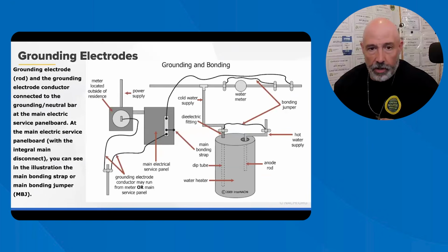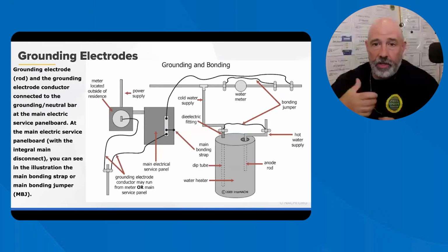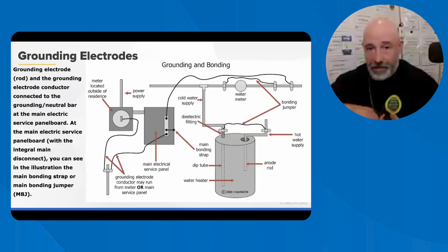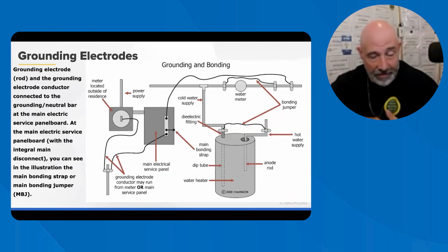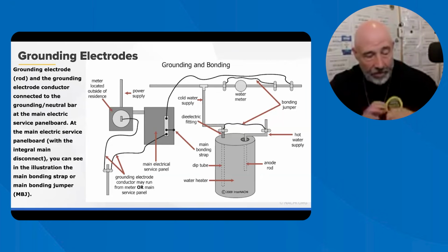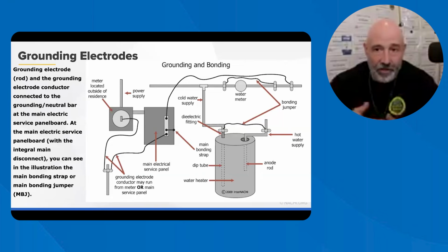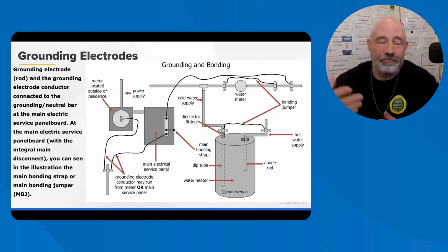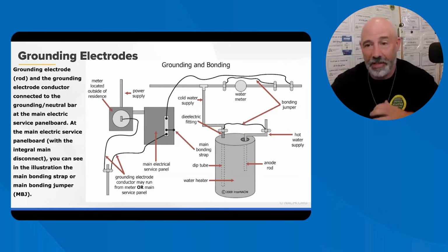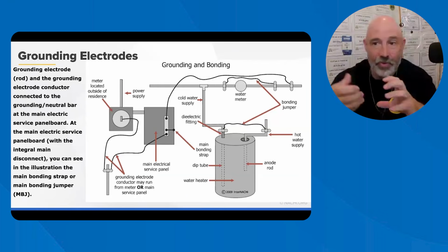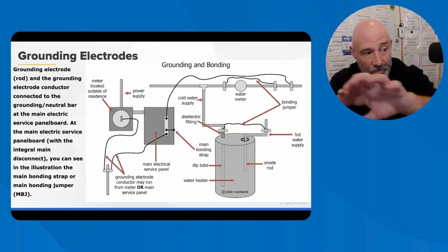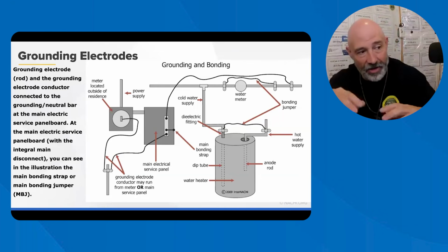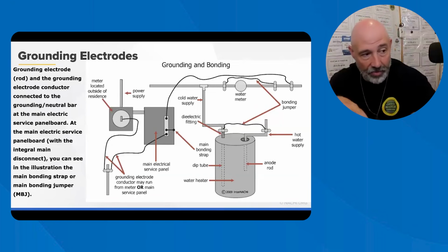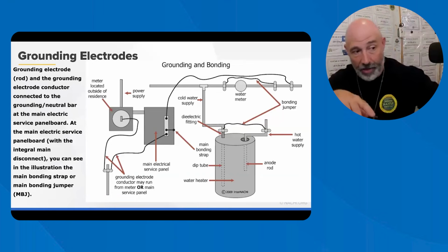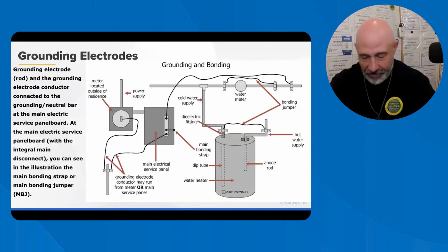A grounding rod is footing reinforcing steel, or normally it is copper. And the metal underground pipes, examples of this system, are all grounded together, or bonded together, I should say, electrically connected together through these terminals, and it all goes right to the earth. So you can see right there how things should be bonded together, even through your water heater there. And if these are all metal pipes, just FYI, you don't want to ground to plastic pipes.